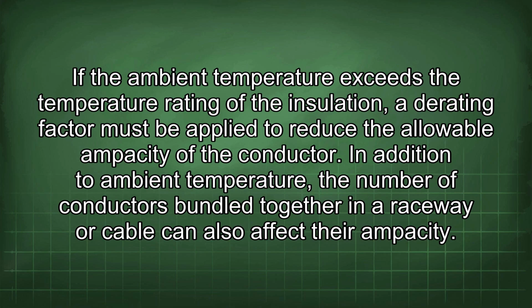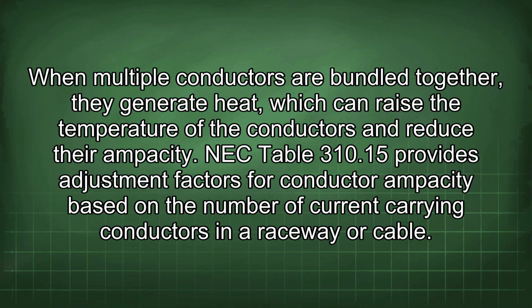In addition to ambient temperature, the number of conductors bundled together in a raceway or cable can also affect their ampacity. When multiple conductors are bundled together, they generate heat, which can raise the temperature of the conductors and reduce their ampacity. NEC Table 310.15 provides adjustment factors for conductor ampacity based on the number of current-carrying conductors in a raceway or cable.